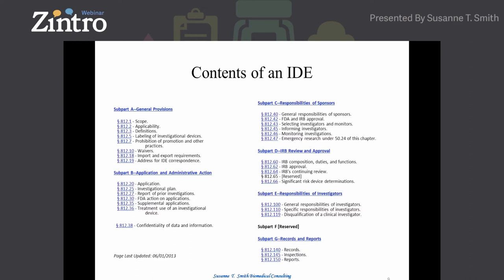Deficiency questions or requests for more information are sent back to the primary reviewer. A letter is compiled and you will receive it within 30 days. In my experience over the last five years, FDA has been very good about replying within 30 days. However, it behooves you to have a very professional, easy-to-navigate document, because if FDA is rushed to the 30-day deadline, you may get more questions than actual guidance. Typically, you will have 45 days to respond to the deficiency letter.